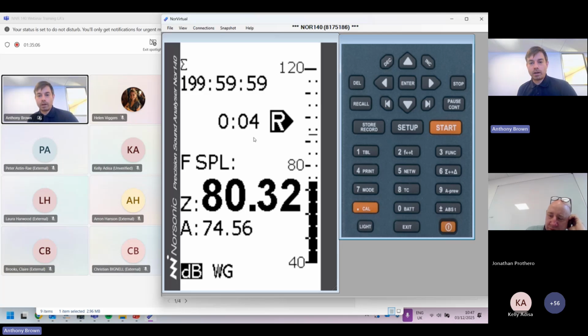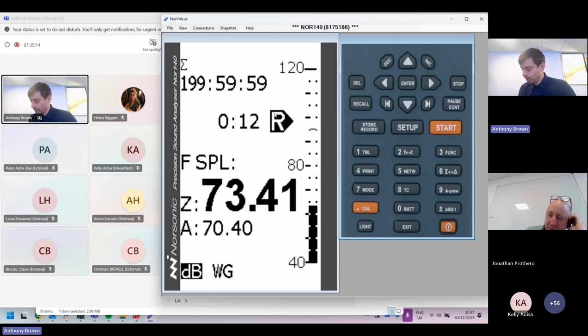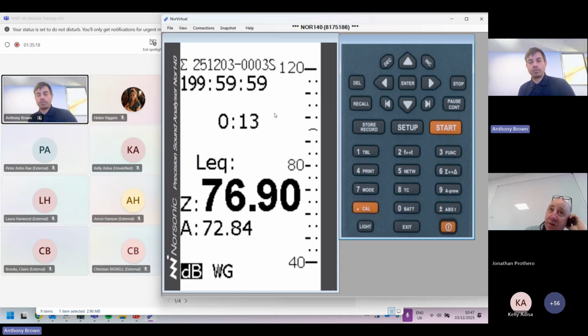So when you press the start button, instead of getting an R you get a W. It's waiting for something to happen, and then it will start recording. I'm going to help you now get rid of that W. Just make sure you've pressed the stop key to get rid of whatever symbol is here. If you've got a W or an R, press the stop button to make sure the measurement's no longer running.